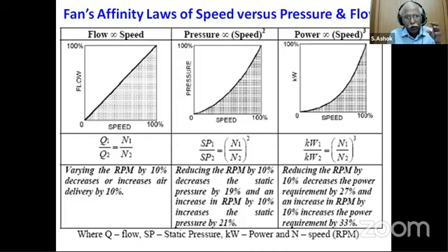When the blower RPM goes down by 10%, power savings of almost 27 to 30% are possible. But the main idea is not to concentrate on the power savings. Let us have the fixed output, and see what input reduction in kilowatts or power is possible. That is what we are looking at. That is called conservation.